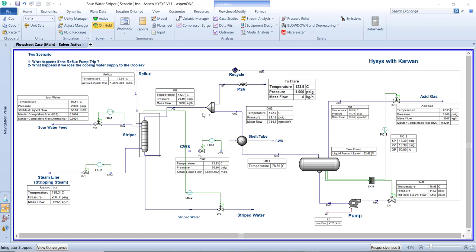The water is boiling above 100°C since the pressure is 21.19 psi gauge. We separate this overhead line into two lines. The first goes to a special cooler — we can call it a shell-and-tube cooler — using cooling water supply. We then send it to a two-phase horizontal separator to separate the gas H2S and get the liquid, which contains ammonia and water. This liquid is recycled back to the tower by a pump to control the top of the tower. The vapor pressure is controlled by a pressure indicator controller (PIC).